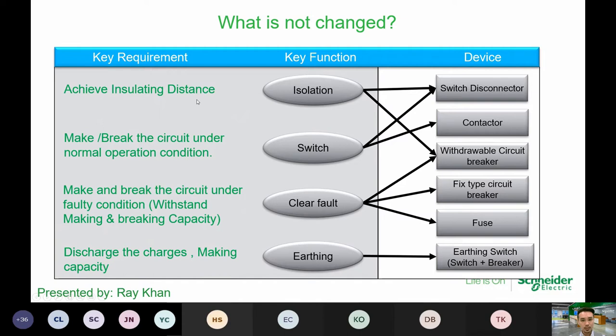All right. So for insulating distance, we need to form isolation. How can isolation be formed? It is via the switch disconnector and also the circuit breaker. Now, the second criterion for a switchgear is that you must be able to make or break the circuit under normal conditions. All right. So by doing this make or break, you also require certain switch features.